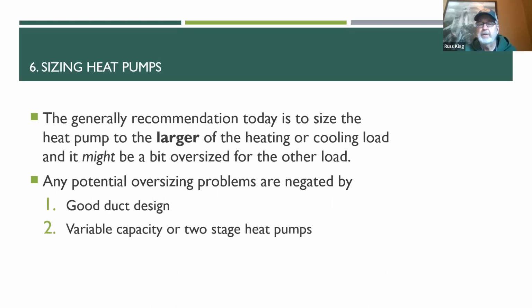The generally accepted procedure for sizing heat pumps today is you size the heat pump to the larger of the heating or cooling load, okay? And then it might be a little oversized for the other load. So you could size it for cooling and it might be a little big for heating, that's fine. You can size it for heating and if it's a little big for cooling, that's fine too. I mentioned earlier that oversizing equipment can cause comfort complaints, but those can be resolved with good duct design and a little better quality heat pump that throttles down on the mild days, okay?